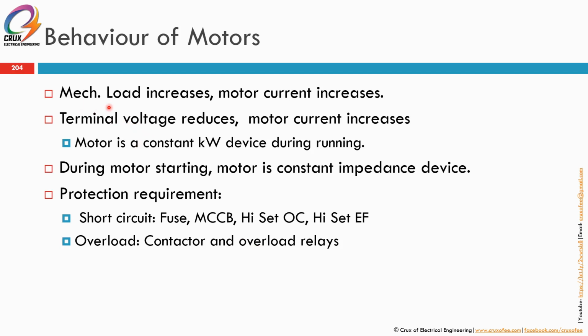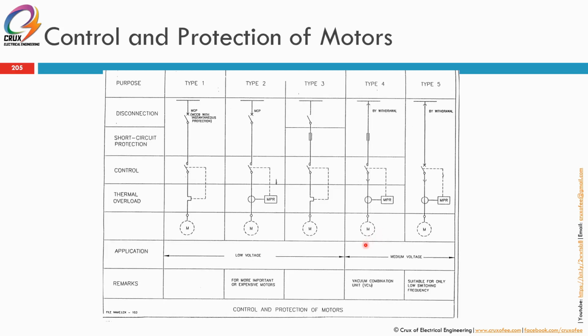As the mechanical load increases, motor current will increase. And as terminal voltage reduces, motor current will also increase. This is because the motor is a constant kilowatt or constant power device during running. During motor starting, the motor is a constant impedance device. Protection requirement: we have short circuit protection, which will utilize fuse, MCCB or high set over current or high set earth fault. And for overload, it is contactor and overload relays. So this is the typical controls and protection of the motor.